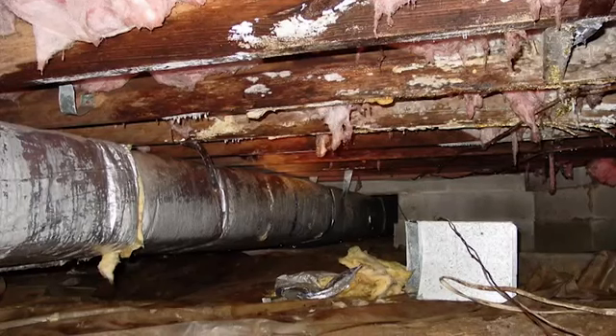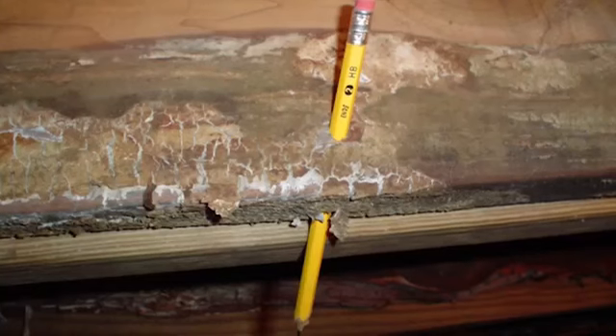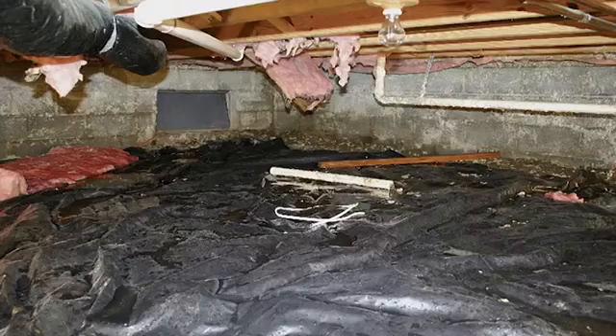In the summer, vents allow warm, humid outside air to enter the cool subterranean crawl space. When we cool that outside air, we raise the relative humidity well above the 70% necessary for mold to grow, the 90% necessary for rot to occur, and condensation forms all over ducts, framing, and insulation. And insects and other pests love damp, dirty, dark places, and they move in.